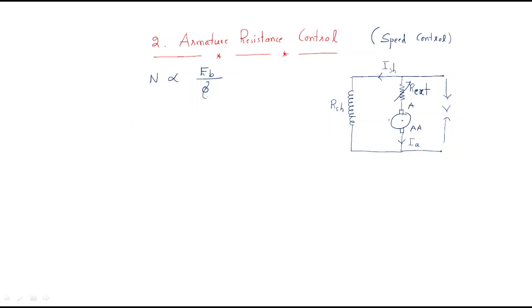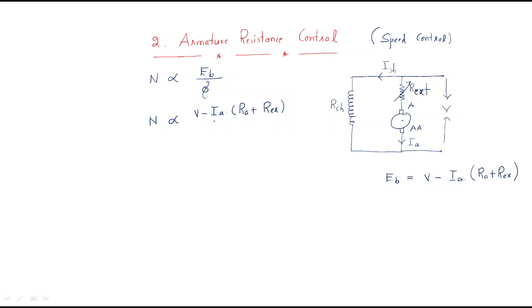The back EMF is generated in the armature. The formula for back EMF is: Eb = V minus the armature drop minus external drop. The external resistance is the series resistance added. So finally, speed is proportional to (V minus Ia × (Ra + R_external)) divided by flux. Since we are using only armature control, the flux is kept constant.